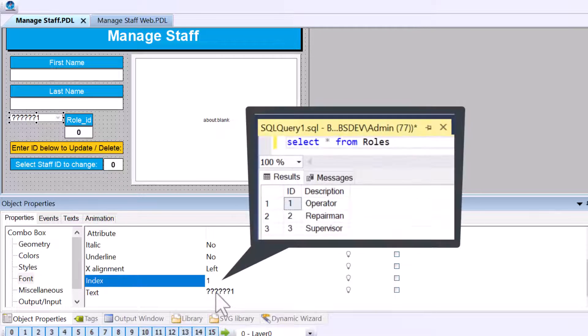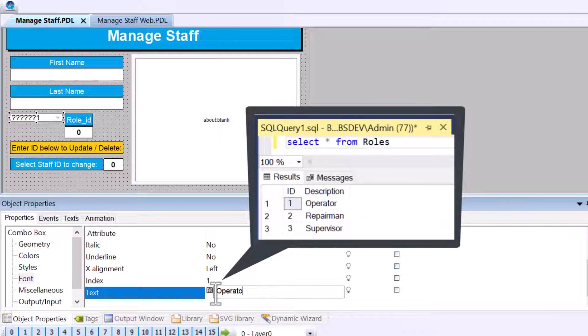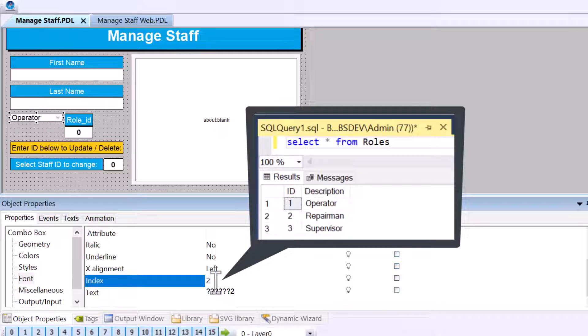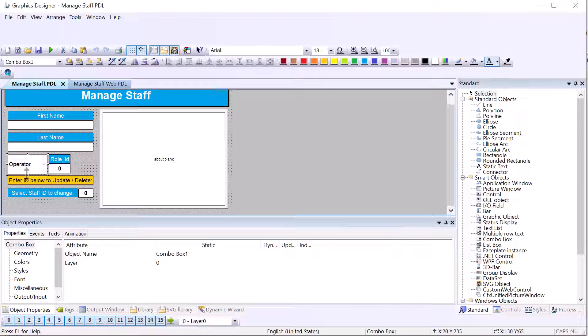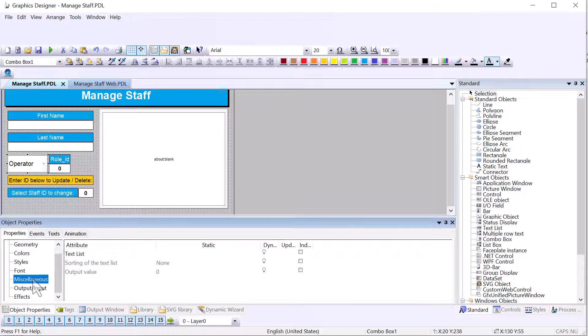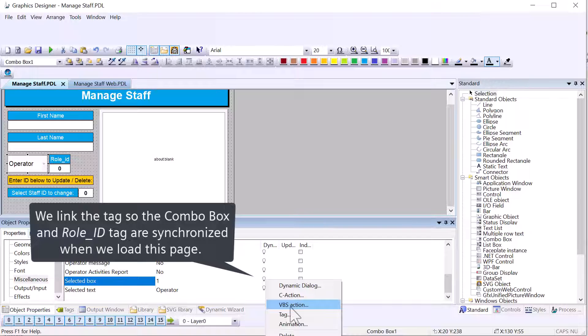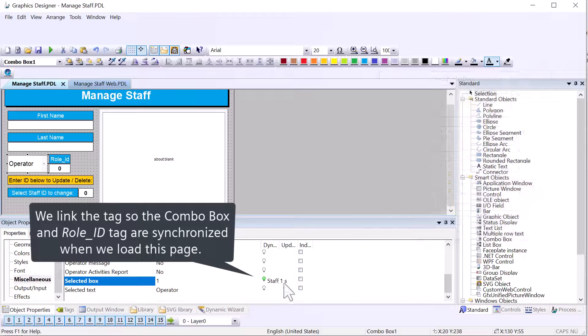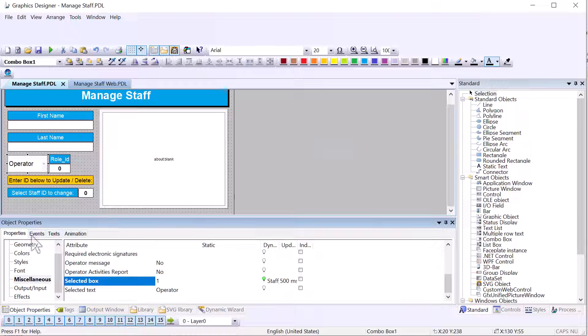The index and text properties work together. For index 1, which correlates to Operator in the database, I'll set the text to 'Operator'. For index 2, 'Repairman'. For index 3, 'Supervisor'. Under Miscellaneous, the 'Selected Box' property is what gets selected — we want to tie that back to our role ID tag so that when they select a role it writes to the tag, and when the page refreshes the tag drives what text is selected. I'll right-click and choose the role ID tag with a 500ms quick update cycle.